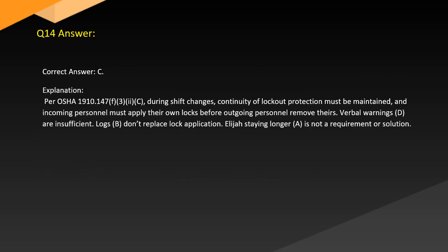Answer. Correct answer: C. Explanation: Per OSHA 1910.147 F3, during shift changes, continuity of lockout protection must be maintained and incoming personnel must apply their own locks before outgoing personnel remove theirs. Verbal warnings, D, are insufficient. Tags, B, don't replace lock application. Outgoing staff staying longer, A, is not a requirement or solution.